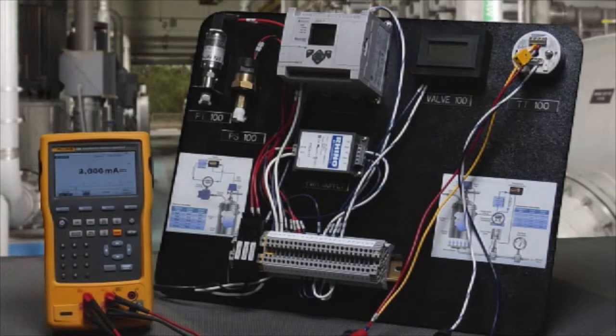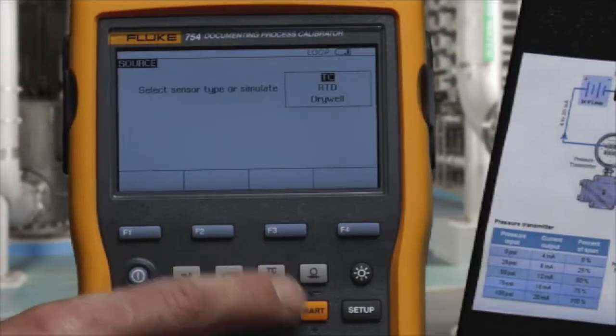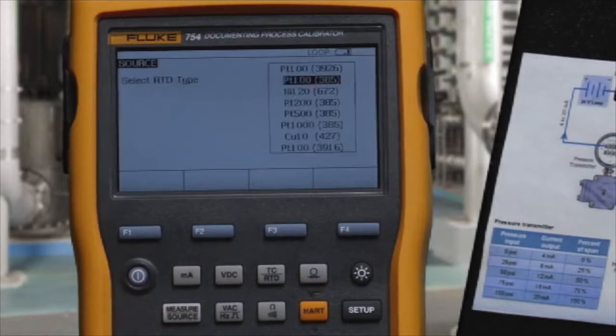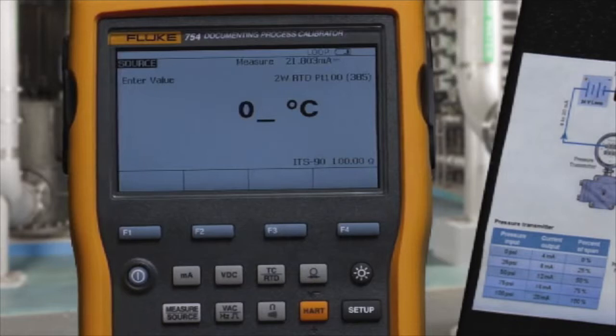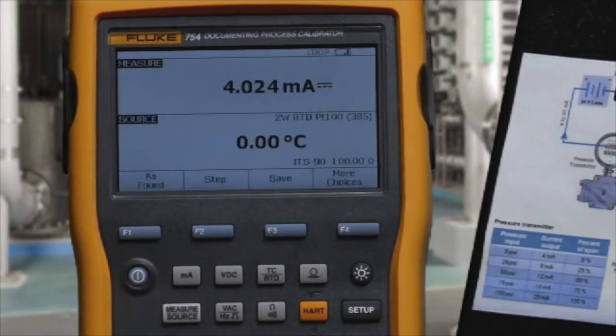Next, we want to configure the input to the transmitter, the RTD source of the calibrator. Select thermocouple RTD and RTD PT100385, input a temperature, and then move to the split screen to document the calibration.